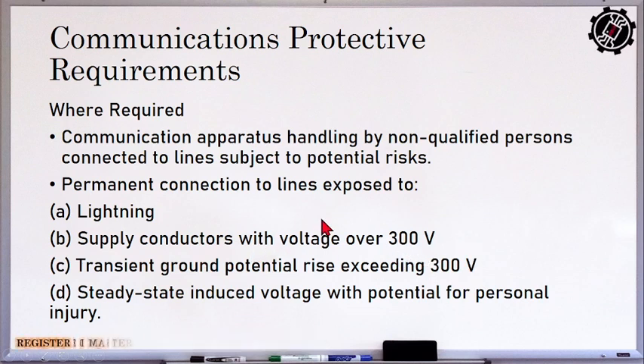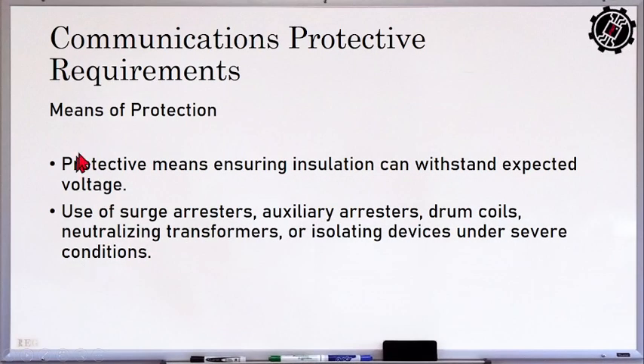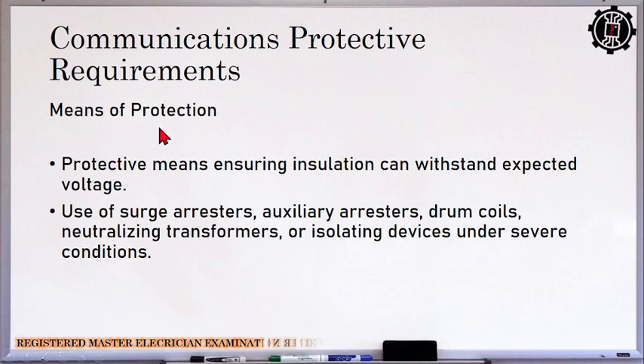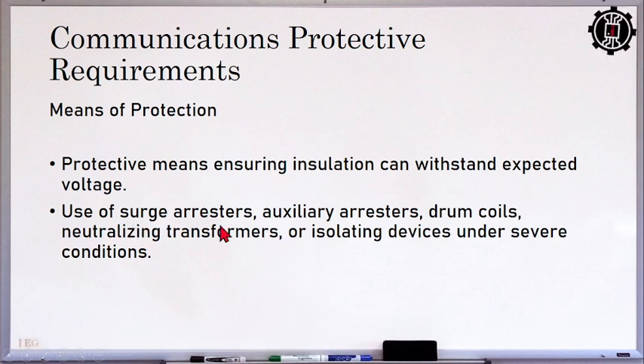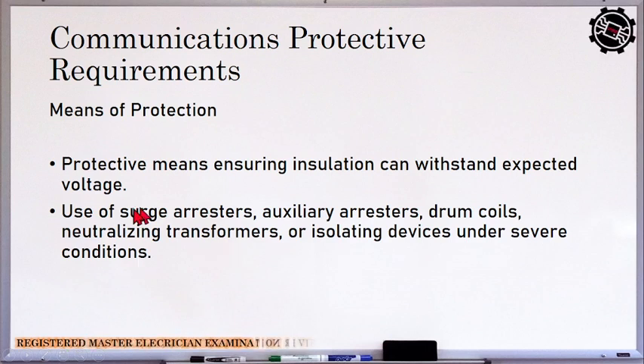So when that happens, there must be permanent communication lines so that the people up there will be able to signal that there is an emergency. Okay. So, means of protection. Aside from the communication system, they will also use a protection system, ensuring the insulation can withstand the expected voltage. Then we go now to our protective devices. We will use surge arrestors, auxiliary arrestors, drainage coils, neutralizing transformers, and isolating devices under severe conditions.